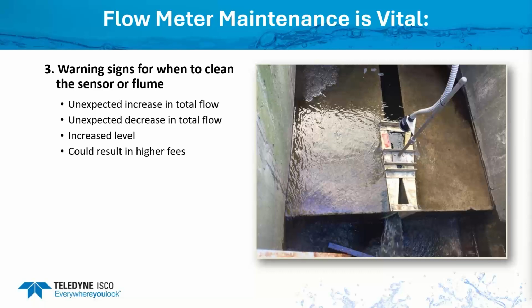You could also look at your level readings, because you're going to see that your levels were normally low, and then all of a sudden now they've tripled or quadrupled. That could be another indication that there's a blockage within your flume. Other things you may notice, like looking at the ultrasonic signal strength, in this case the signal strength actually went up, because looking at this picture, the water is fairly smooth when it's higher, and when it was lower, it may have been a little bit more turbulent. So you may see that it went from like 80% up to 90%. That could be another indication that there's some type of a blockage in that flume.